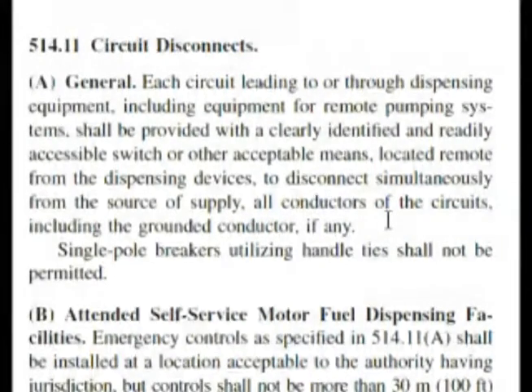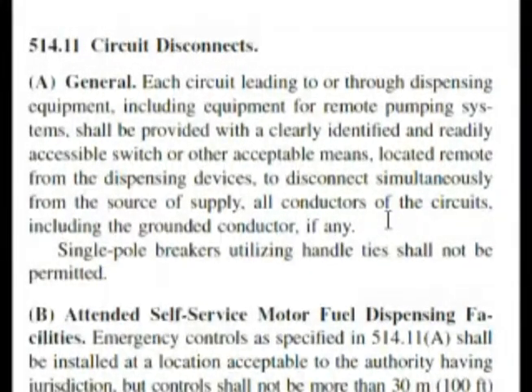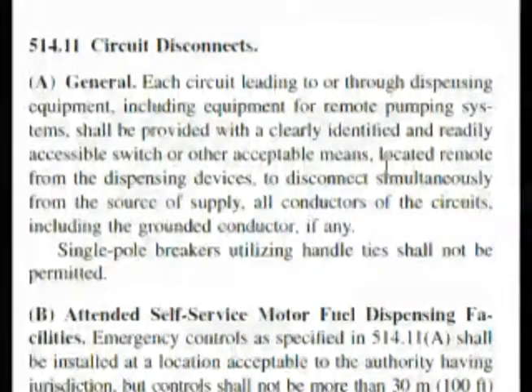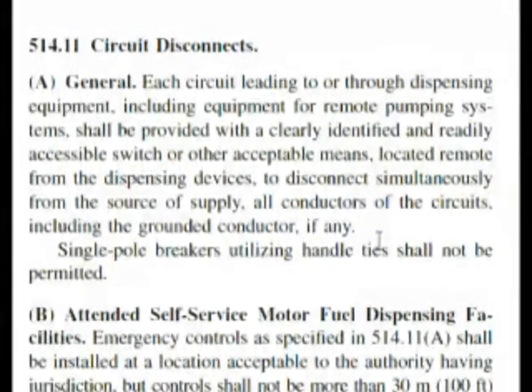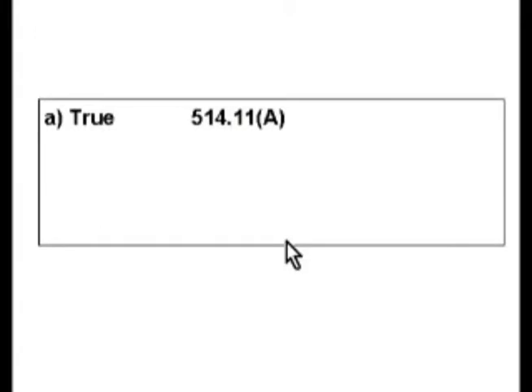Simultaneous disconnection is very important — you want everything to go off at the same time, not circuit by circuit. If you've got fuel dispensing, sparks, and a potential problem, you want it all to shut down right away. Our question was a little poorly worded because it should have included this aspect of simultaneous disconnection. Even so, the answer is obviously true, and it makes common sense: in an emergency, you want to shut it all down completely at the same time.